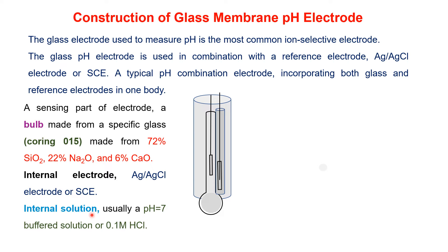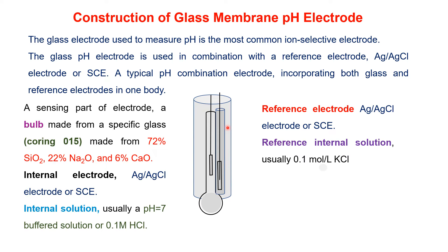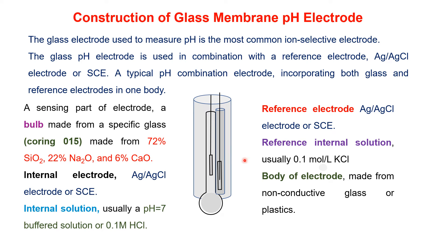The third part is the internal solution, which is either a buffer of pH 7 or a 0.1 molar hydrochloric acid solution filled in the bulb. The reference electrode is either a silver-silver chloride electrode or a calomel electrode. The reference internal solution is 0.1 mol/L potassium chloride, and the body of the electrode is made from non-conductive glass or plastics.